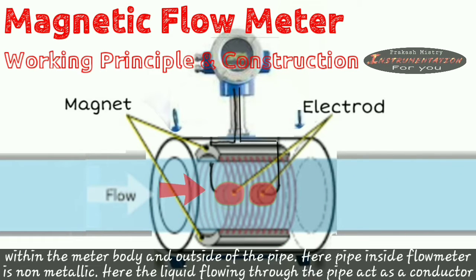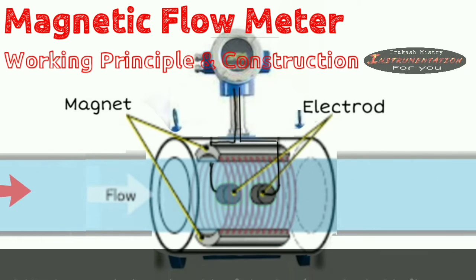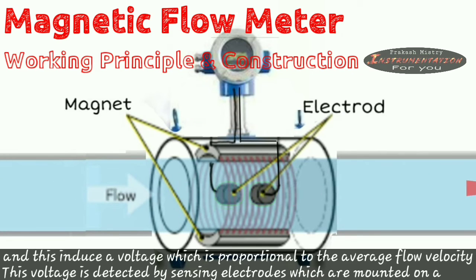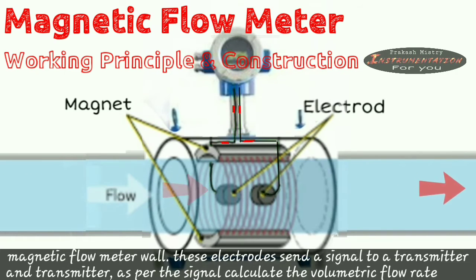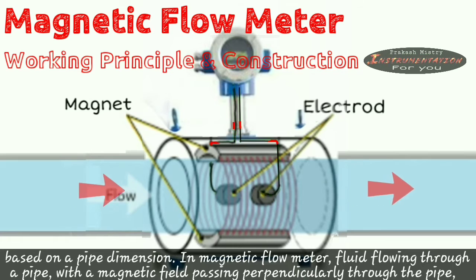Here the liquid flowing through the pipe acts as a conductor and this induces a voltage which is proportional to the average flow velocity. This voltage is detected by the sensing electrodes which is mounted on the magnetic flow meter wall. These electrodes send a signal to a transmitter, and transmitter as per the signal calculates the volumetric flow rate based on the pipe dimension.